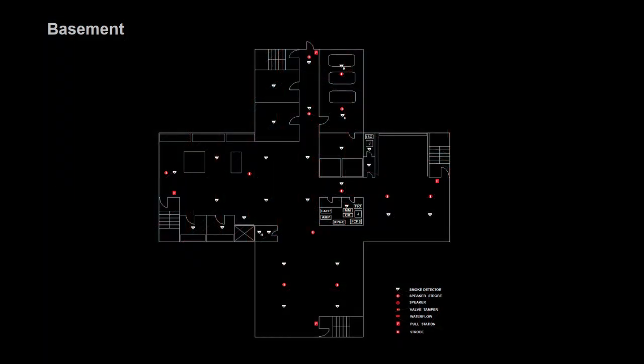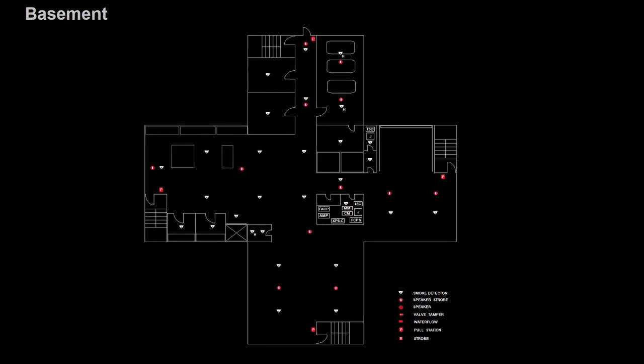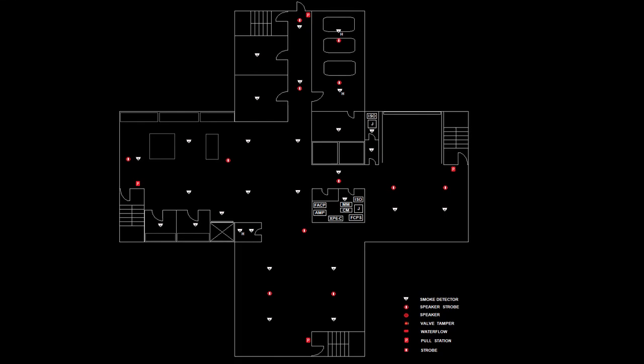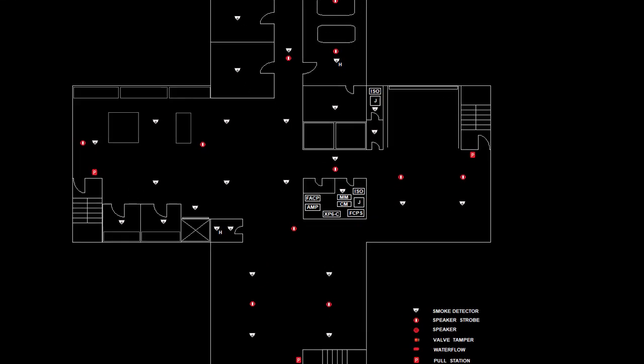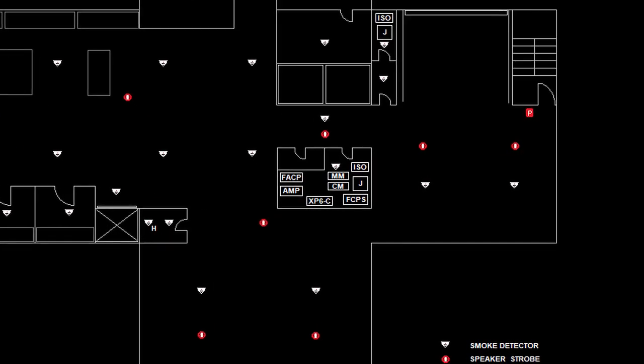Suffice it to say that the SLC will leave the fire alarm control panel in one conduit, hit each device in sequence, and then return back to the panel in a separate conduit maintaining at least five feet of separation between the two conduit runs wherever possible.